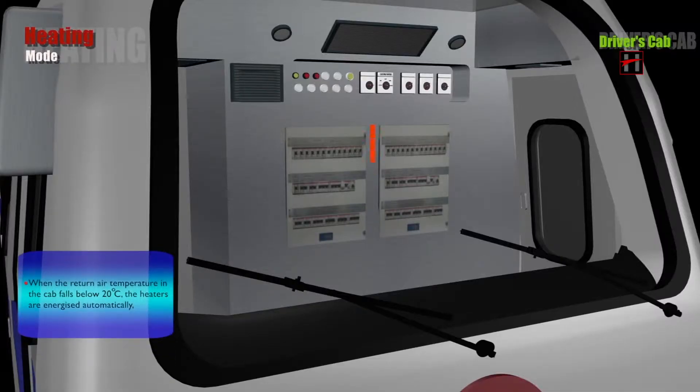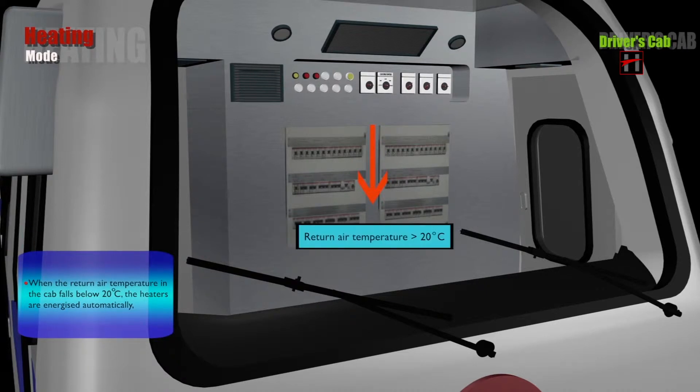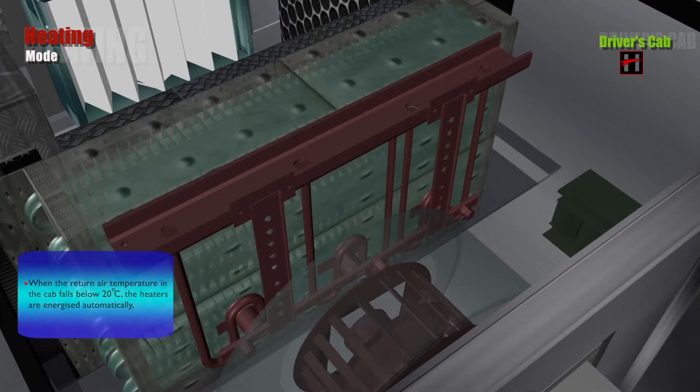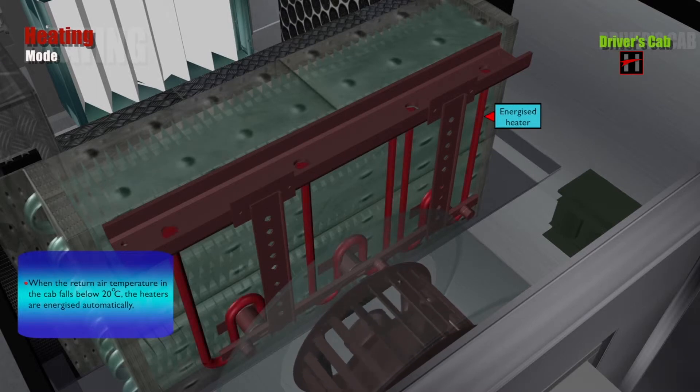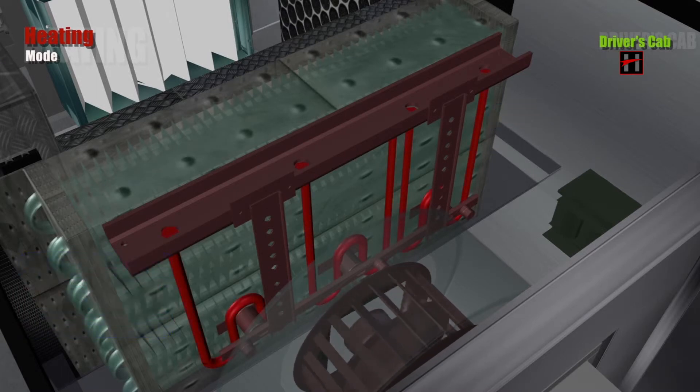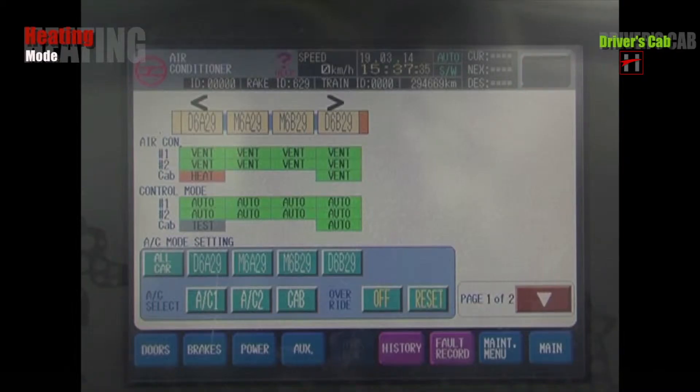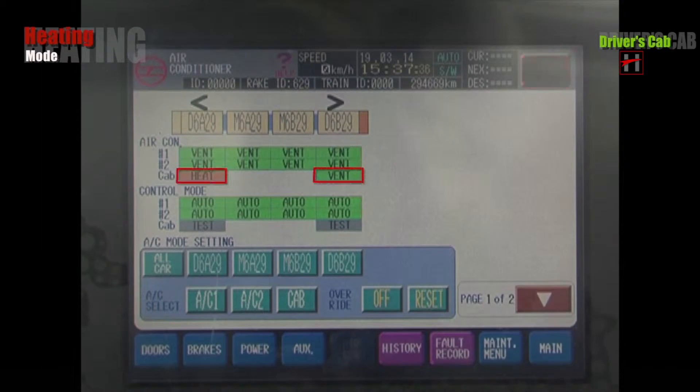When the return air temperature in the cab falls below 20 degrees Celsius, the heaters are energized automatically and heat is indicated on the TIMS HVAC display.